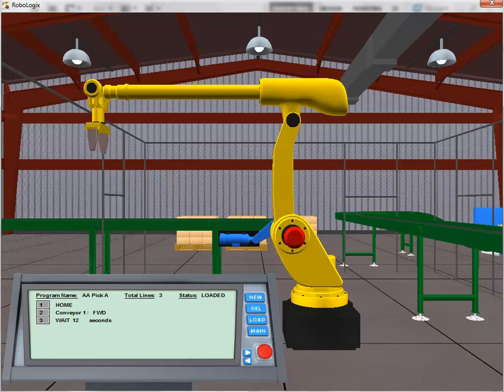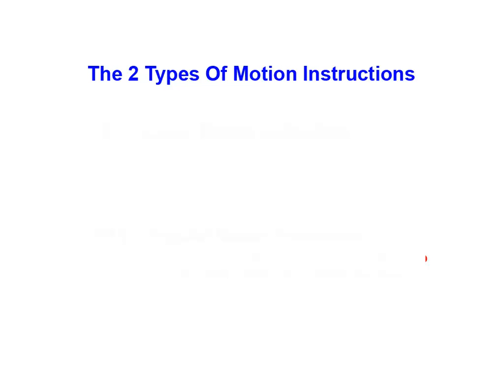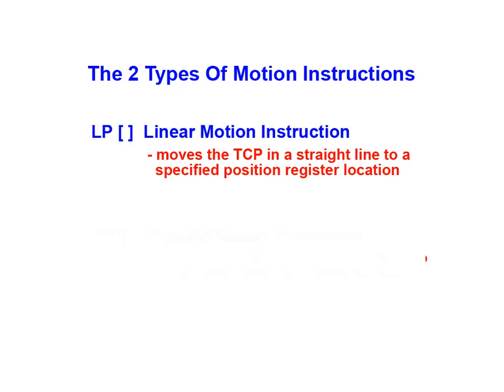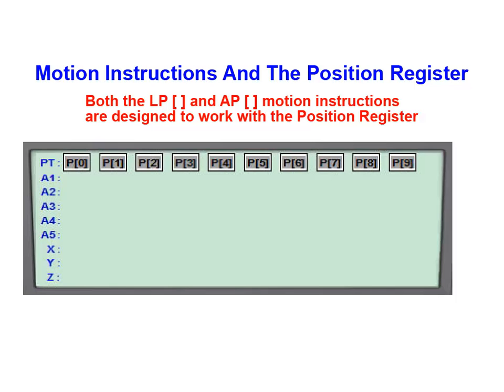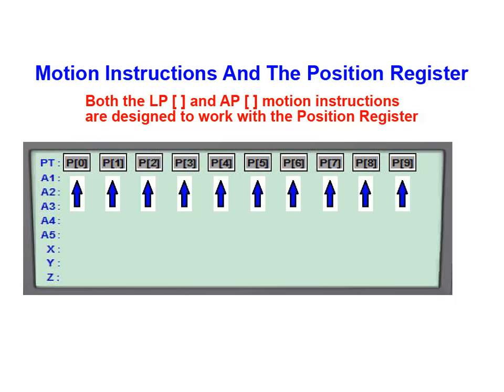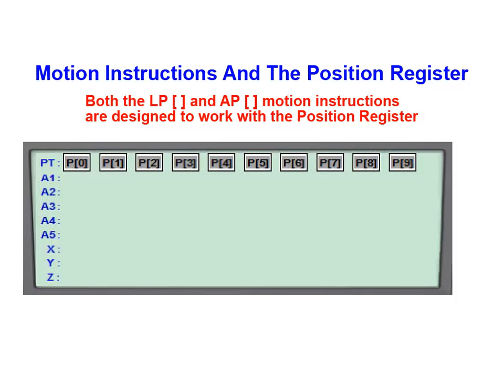We're now ready to add an instruction that'll move the tool center point to a position directly above the box. RoboLogix provides two types of motion instructions. The first is the Linear Motion instruction, which moves the tool center point in a straight line to a specified position register location. The second is the Angular Motion instruction, which moves the tool center point in an angular motion to the specified position register location. Both motion instructions work with the position register, which is capable of storing up to 10 distinct tool center point positions, indexed 0 through 9.